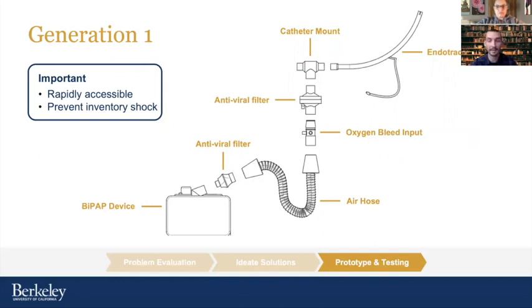So the way this device transports air to the patient is basically this device sucks in air, it goes through an antiviral filter to take out those aerosolized COVID-19 particles. It then goes through an air hose and then into an oxygen bleed port, which is where the hospital could provide additional oxygen if the patient needed it, up into another antiviral filter, which allows for exhalation here. So that way no exhaled air is being emitted with COVID-19 particles. And then up to a catheter mount and an endotracheal tube.